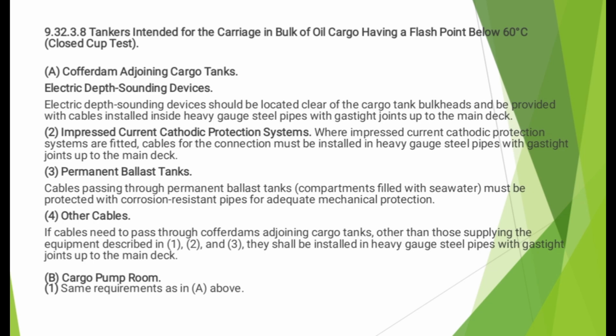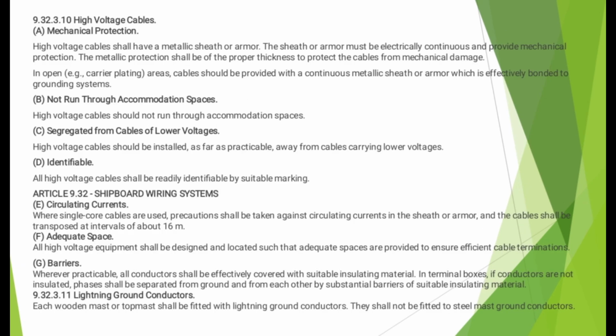Cargo pump room. Same requirements as in A above. High voltage cables. Mechanical protection. High voltage cable should have a metallic sheath or armor. The sheath or armor must be electrically continuous and provide mechanical protection. The metallic protection shall be of the proper thickness to protect the cables from mechanical damage.